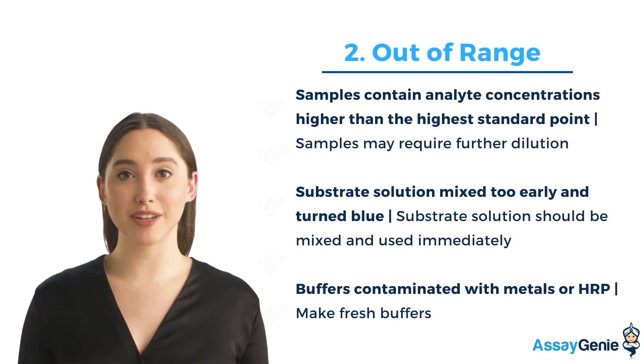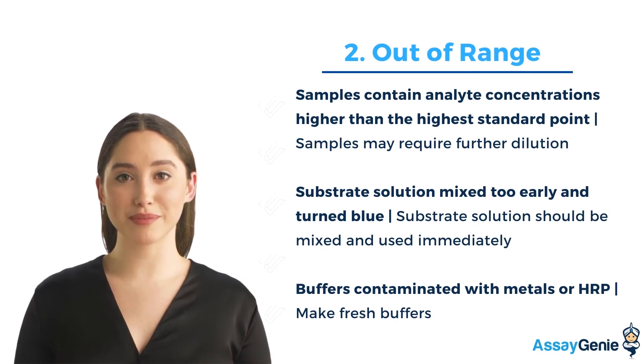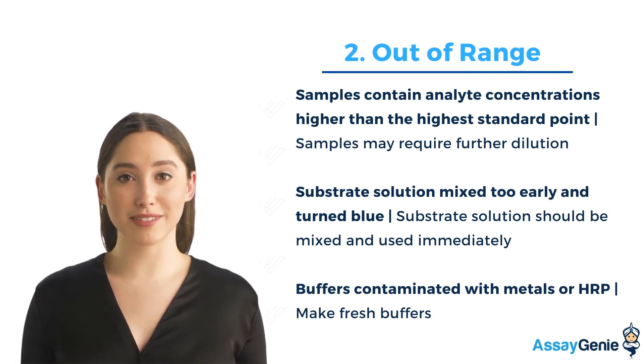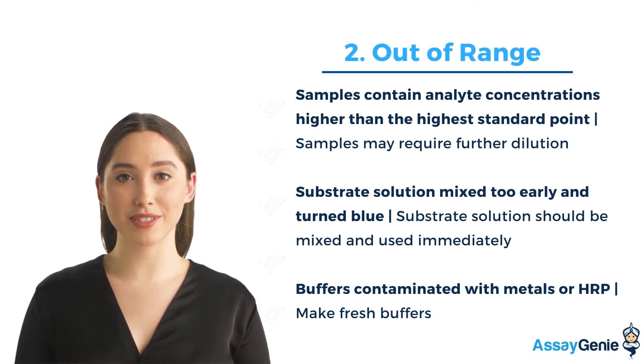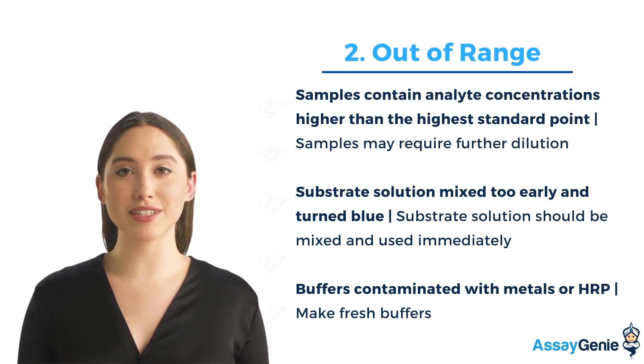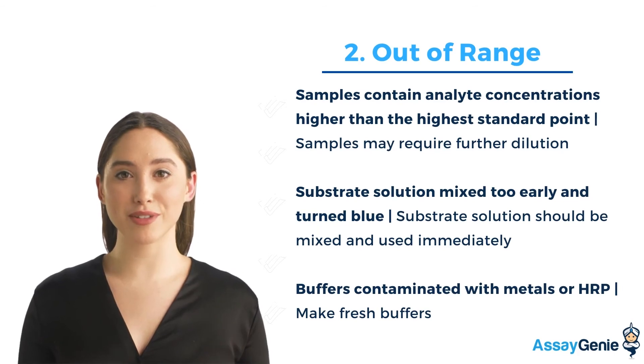If your results are out of range, this may result in a loss of data due to negative or no results. Common reasons for out-of-range results include the sample containing too high a concentration of analyte, incorrect buffer, or dilution preparation.